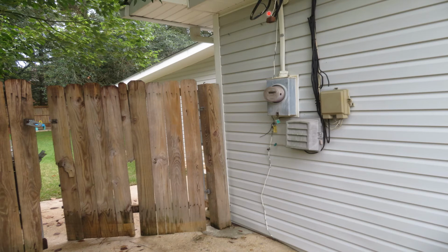That's what this drip loop is, and that's what was missing in the other slide. If you have this situation, you really need to correct it, because as shown in one of the previous slides, this insulation can get old and very brittle. So if you're walking around with a ladder and happen to bump this with the ladder or a paint pole or anything else, it can create an electrocution hazard.